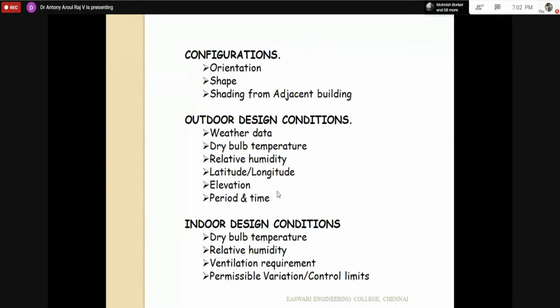For example, if you are maintaining at 25 degrees and 50% RH, it may consume one electrical unit. If you go for 18 degrees and 40% RH or lower, it may consume 3 units. So from the energy point of view, and for initial design point of view also, this is very important. Indoor design conditions—dry bulb temperature and relative humidity—are two important things.